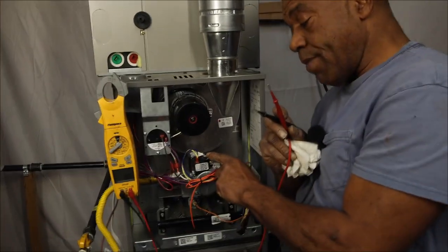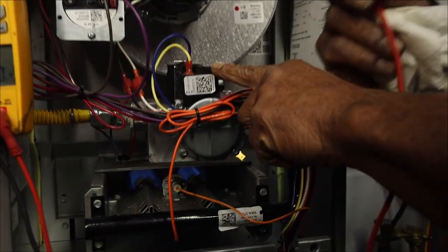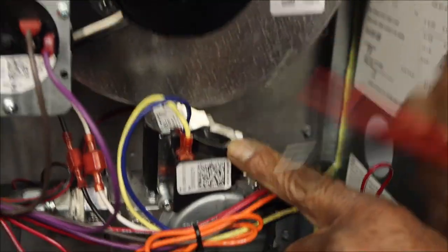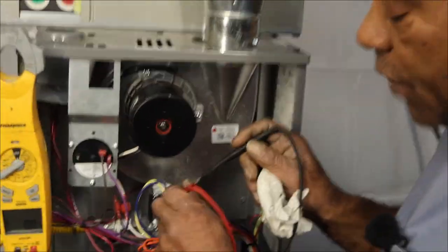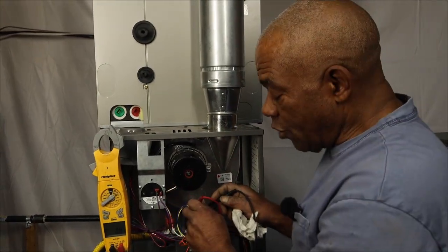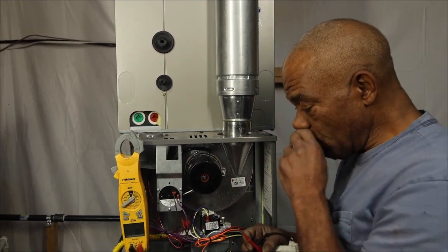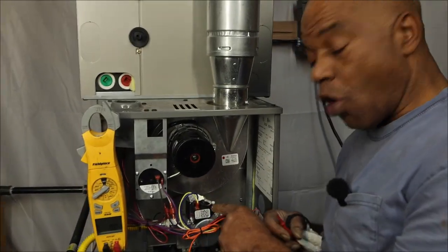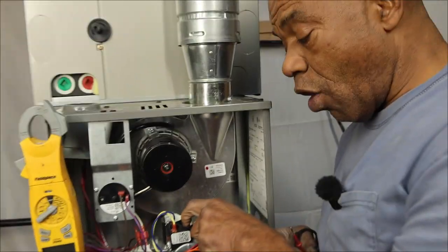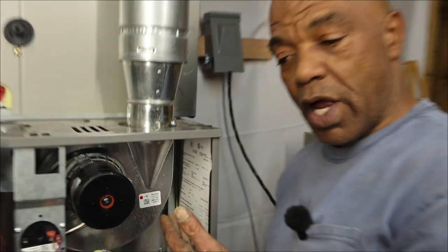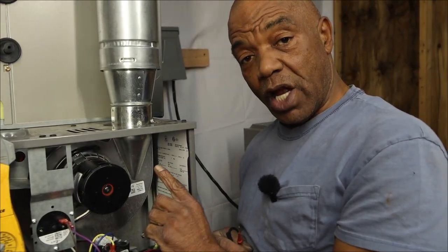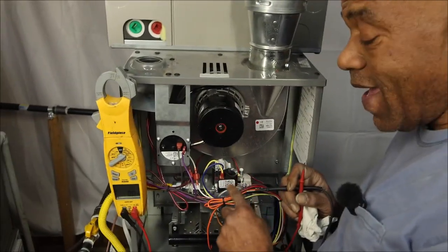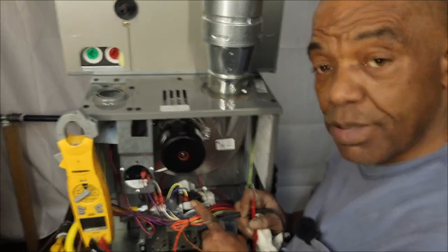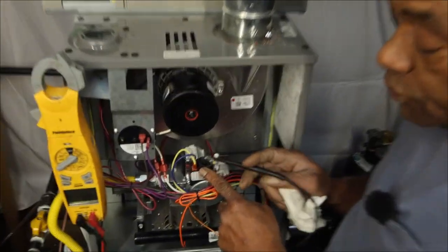But if I were to look at my gas valve and I wanted to verify whether my gas valve was working, unfortunately, the way it's connected, I can't get my lead down in there in order to test it while it's running. But if, for instance, I'm going to cut the power off on the gas valve for a moment, I'm going to cut the power off. That shut the gas off because I turned it off, but it'll allow the fan to keep running so it can cool the unit down before I shut it off. Now, if I had a problem or a suspected problem with my gas valve, I would pull these wires, both of them off.